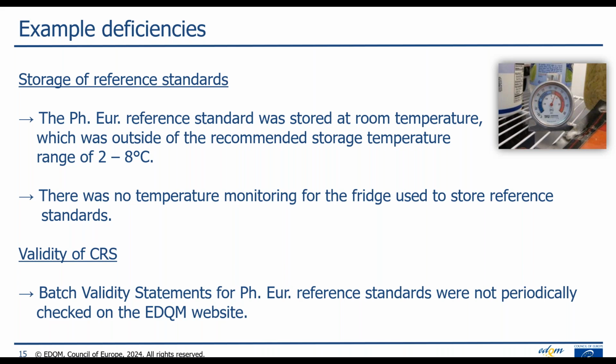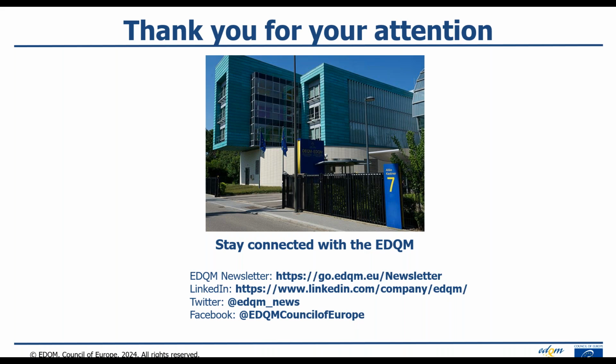And then in some other cases, we might find that there's no temperature monitoring of the fridge being used to store the reference standard. Then in terms of the batch validity statements, this is another relatively common deficiency whereby the batch validity statements are not being checked to ensure that the reference standards being used are valid at the time of use.